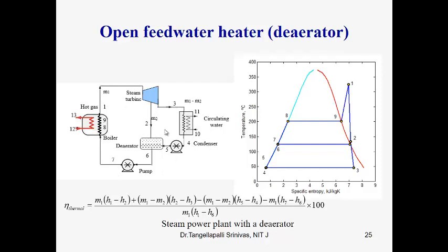In this category, the open feed water heater is also called a deaerator, because the dissolved gases in the steam or water are expelled out in the deaerator. They are not able to condense into liquid form, they remain in the gaseous form. That's why they are trapped out.